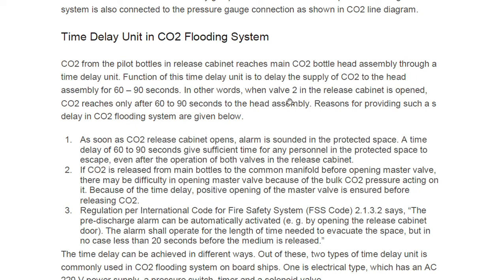In other words, when valve 2 in the release cabinet is opened, CO2 reaches the head assembly only after 60 to 90 seconds — the exact delay depends on the system and design. The reasons for providing such a delay in the CO2 flooding system are as follows: as soon as the CO2 cabinet is opened, an alarm is sounded in the protected space, and the time delay of 60 to 90 seconds gives sufficient time for personnel to evacuate.